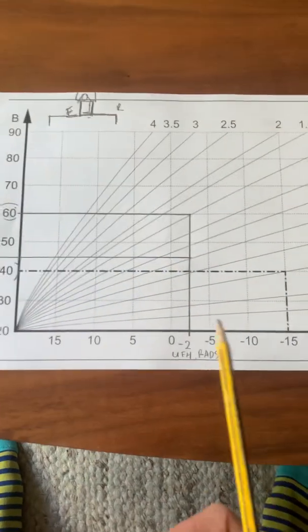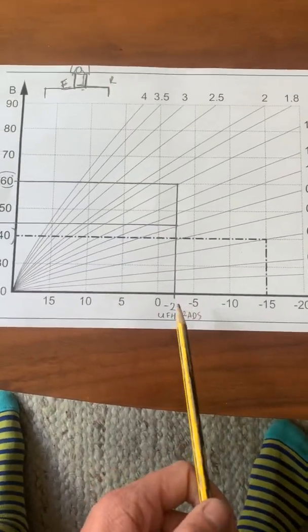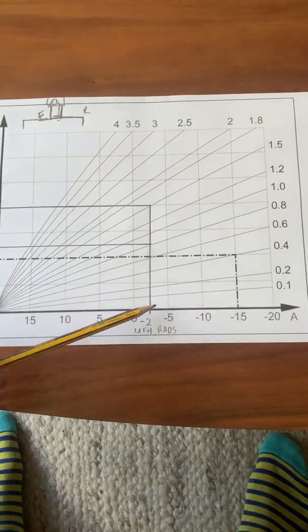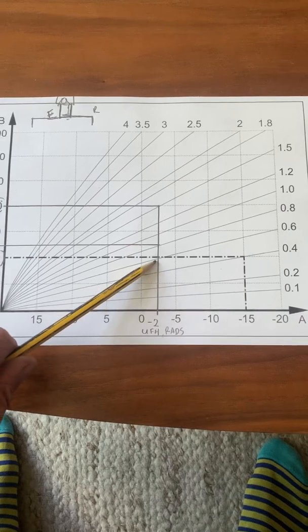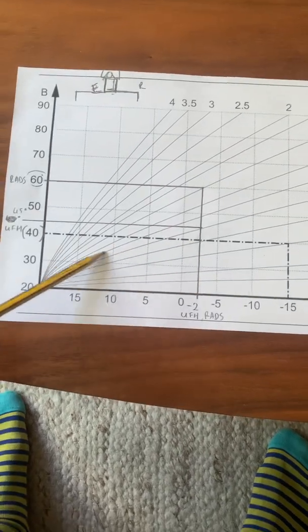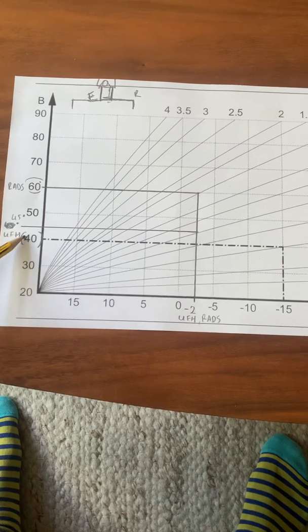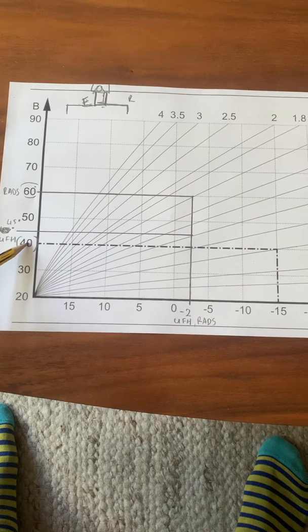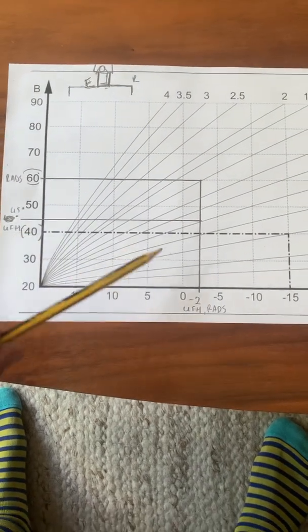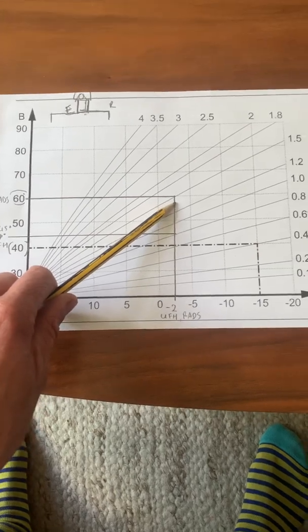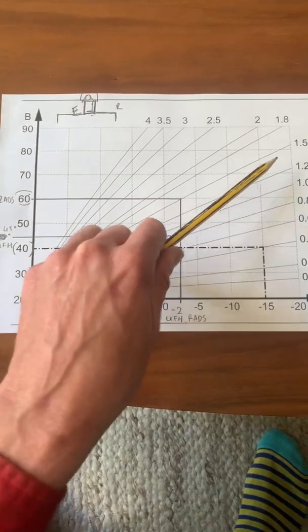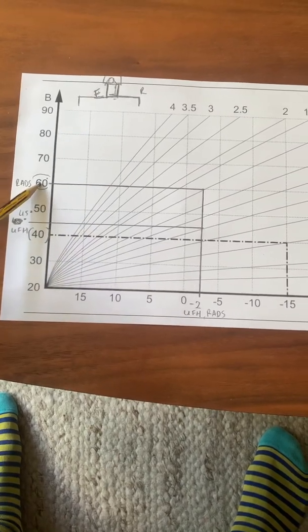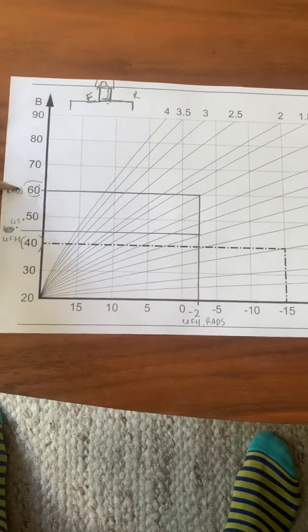So for instance, underfloor heating at minus 2, where I am in London, I have set it to 0.6. We come across and that will give me a 40 degree flow, so the flow to the underfloor heating at minus 2 will be 40 degrees. Then the radiators, same minus 2 where we are in London, those with a 1.5 curve will be a 60 degree flow temperature, so the boiler should be trying to achieve 60 degrees.